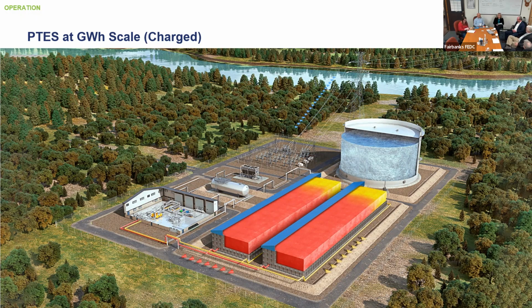Okay, where is the control for that fluid flow, the phase change throughout the system? Right, so the system itself has a high and low pressure side. When I'm running a heat pump, I have a gas compressor that takes the vapor CO2 and increases its temperature and pressure at the same time.